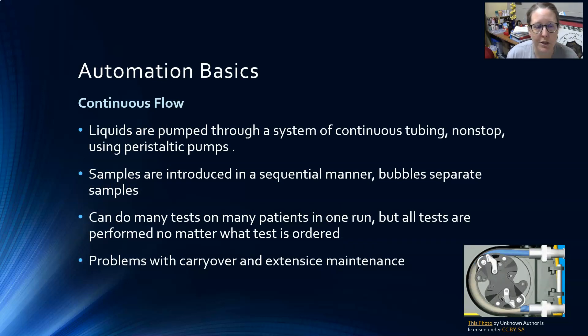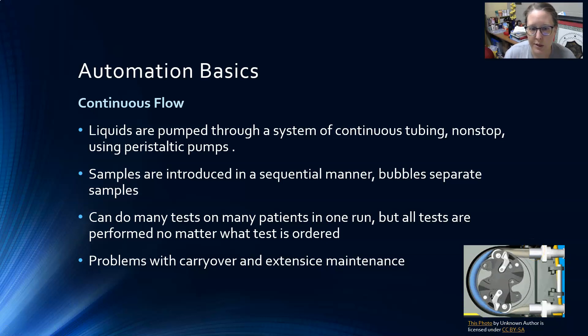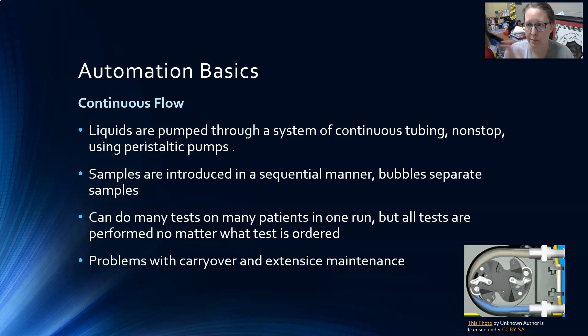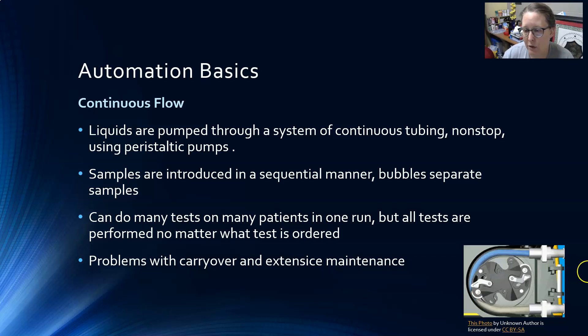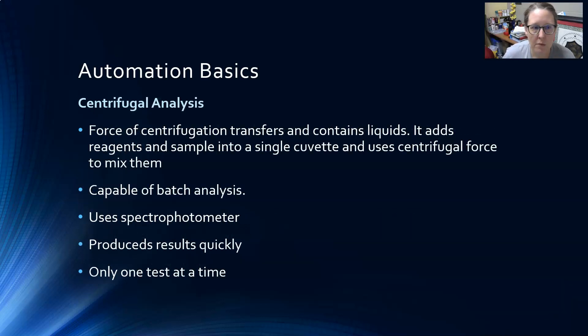For continuous flow analysis, liquids are pumped through a system of continuous tubing non-stop using peristaltic pumps. This illustration shows a peristaltic pump at work — samples are introduced in a sequential manner and bubbles separate the samples. You can do many tests on many patients in one run, but all the tests the machine performs are run regardless of what test is ordered — it doesn't have the capacity to single out individual tests. There are also problems with carryover and extensive maintenance, as substances from one specimen can stick to the tubing and contaminate the next sample.